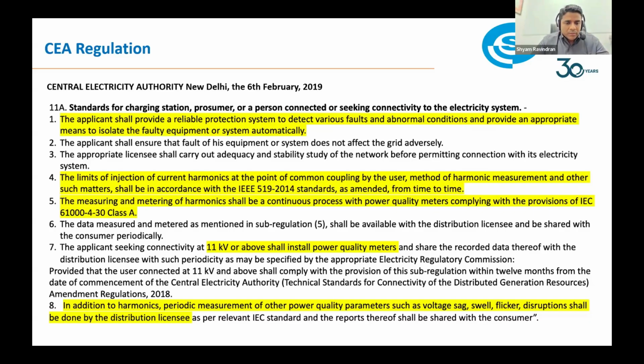The limit of injection of the current harmonics at the point of common coupling by the user, method of harmonic measurements, and other such matters shall be in accordance with IEEE 519/2014 standards as amended from time to time. Now the standard is amended to 2022, so naturally this regulation has to be followed up to the IEEE 519/2022 standard. So who is this applicable to? The applicant seeking a connectivity of 11 kV or above shall install power quality meters. So basically the bulk consumers, from this definition point of view, because way back in the definitions also, rather than a kV rating, a term called bulk consumers was used.